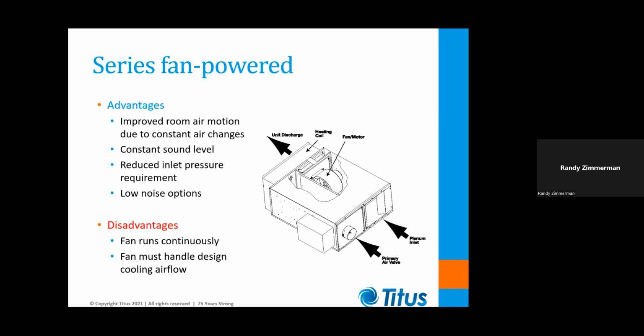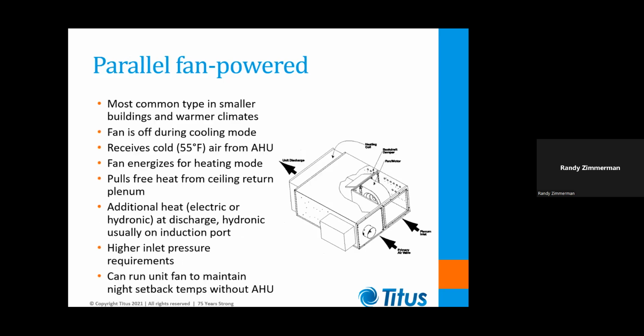Now, the disadvantages of the series fan box would be, hey, the fan's got to run all day long, and the fan has to be large enough to handle the cooling design airflow. So the fan in a series fan box could be twice as large as the fan in a parallel fan box. But let's look at that parallel fan box. And you can see here in the cutaway, the motor blower assembly is set back inside the unit on a parallel fan box, and the fan only runs during the heating mode.